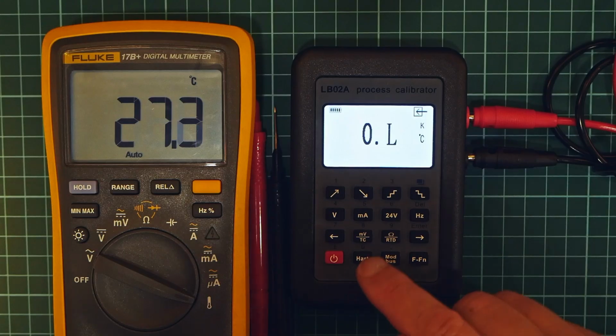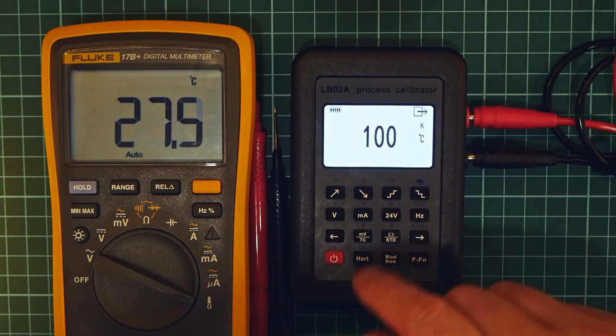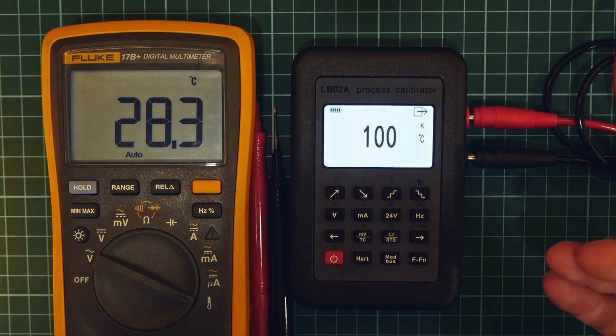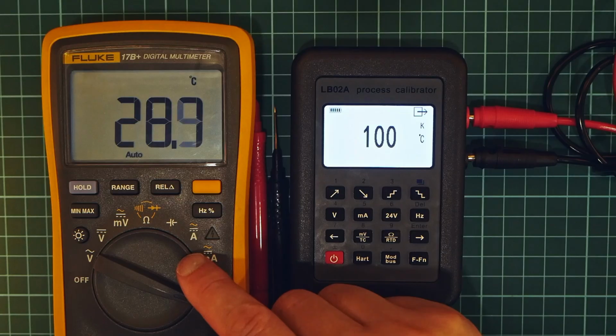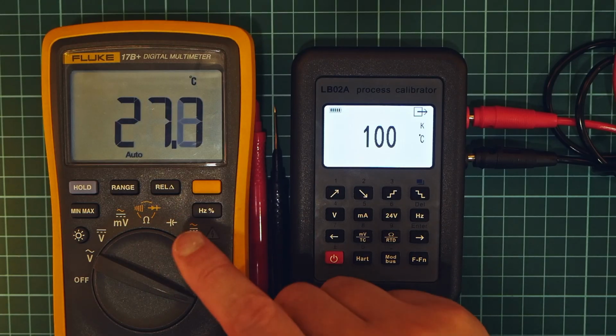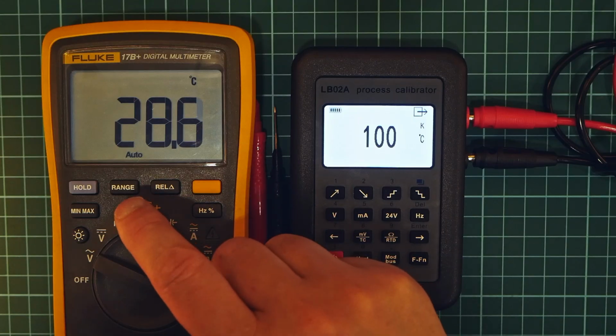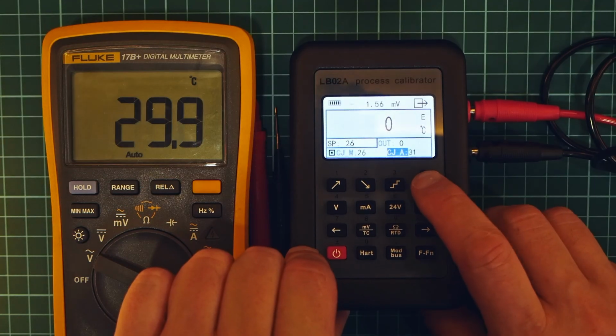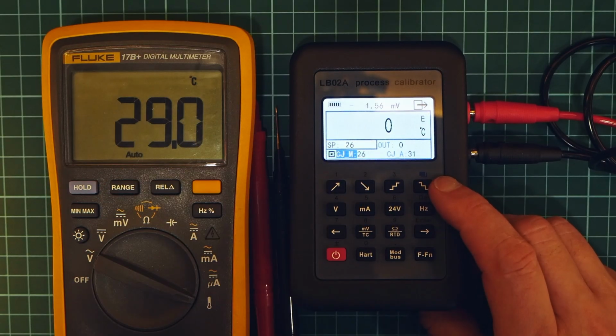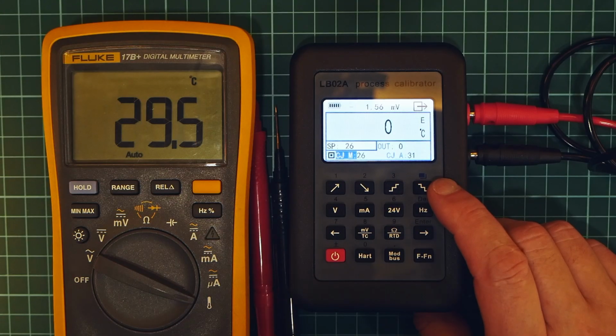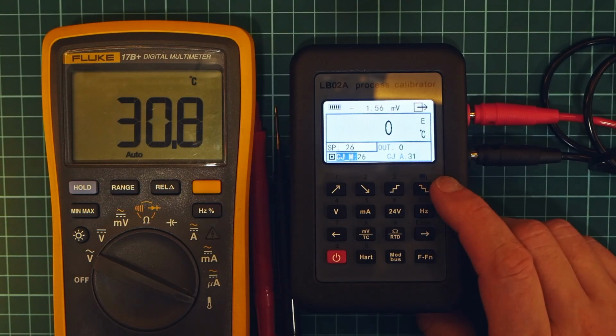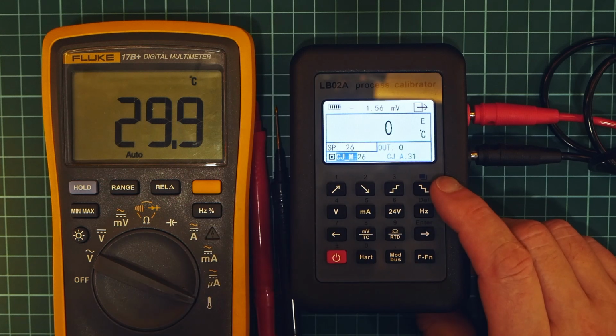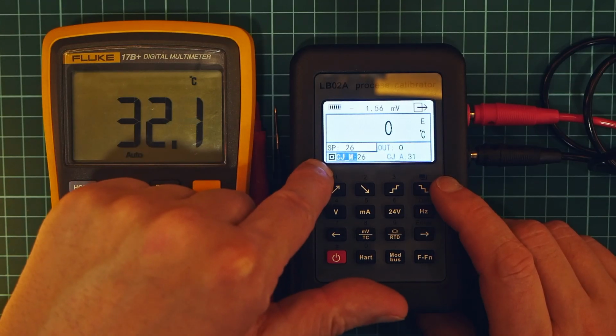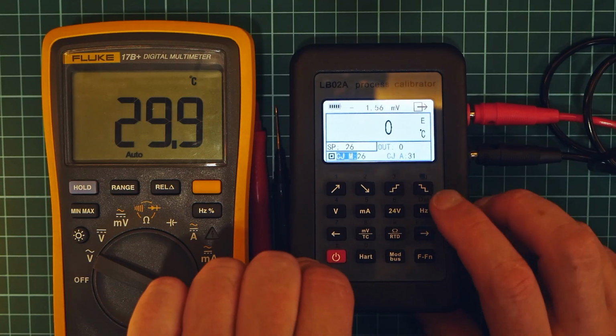Right now we are in thermocouple mode; we press it again. Right now we are in output mode. Yes, so let's say that this is not a multimeter, but an analog thermocouple input card. We're measuring millivolts on this analog input, and we need to enter a cold junction of 26. Basically, this is the ambient temperature. So you can use automatic cold junction, but in this case it will be 31, which is way outside the range, and you will have a bad reading. So yeah, always select manual cold junction.